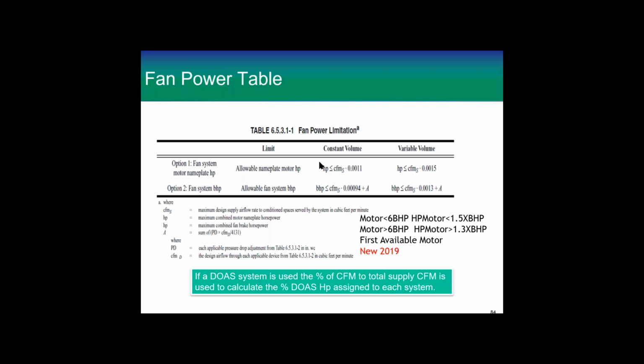And so then as you get to the end with this brake horsepower, if your motor is less than 6 brake horsepower, then the motor you actually install can be 1.5 times that brake horsepower. If it's the other way, that's 1.3, and the first available motor bigger than that number. So you get a little break there on how much horsepower you're putting in too. So there's a lot of advantage to option 2, but if you just qualify under option 1, then it's no use to go ahead.